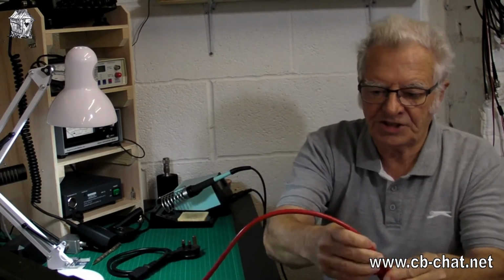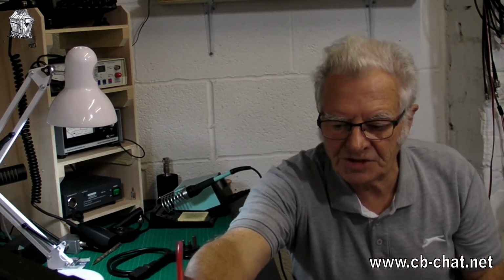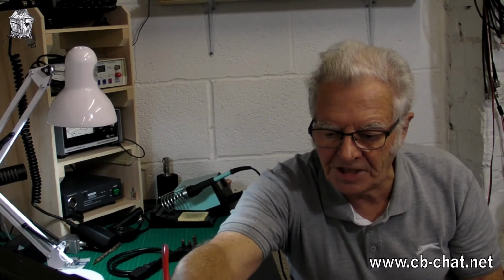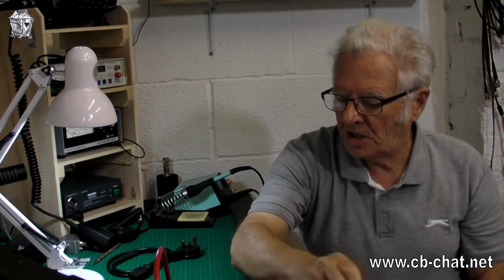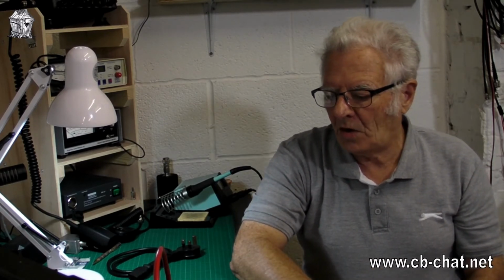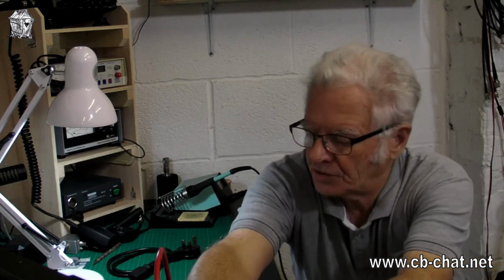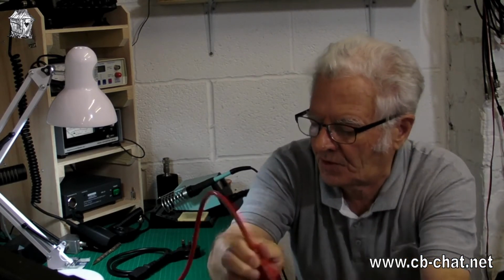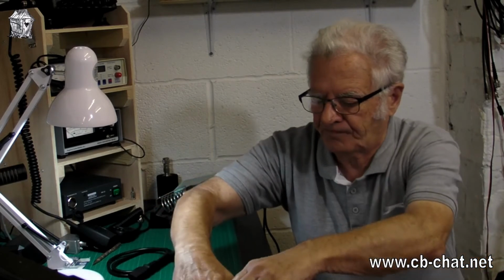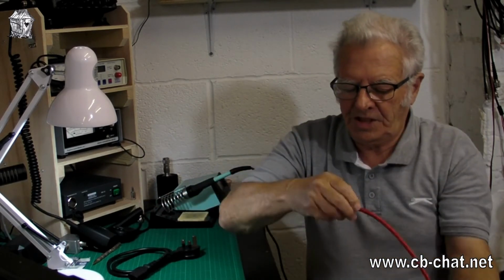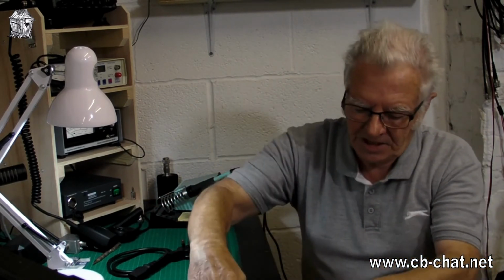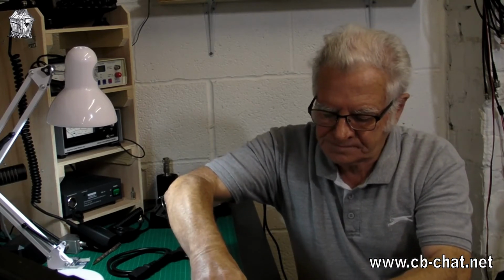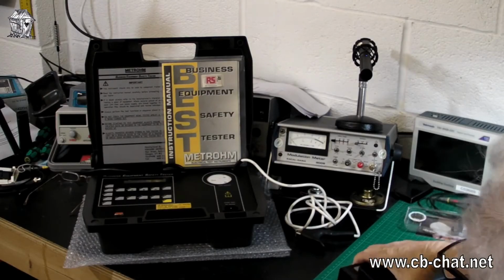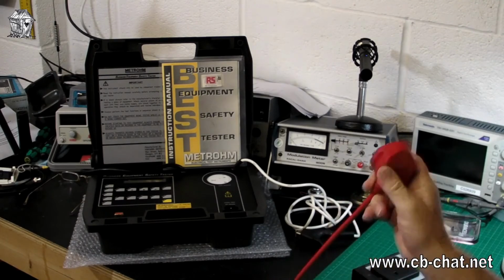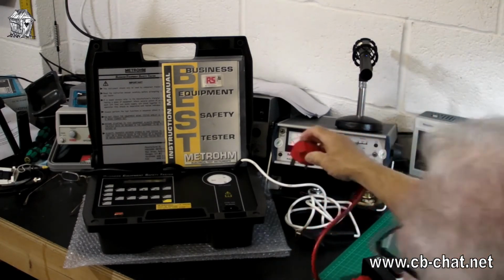We'll plug it into the tester where it says mains lead, there, IEC mains lead. We could do it that way, or we could do it the other way. It makes no difference really. We'll do it the other way, so it's more like an appliance. We'll put the IEC lead in the bottom there. Now it's more like an appliance that we're testing, and we'll plug it in to the PAT tester.